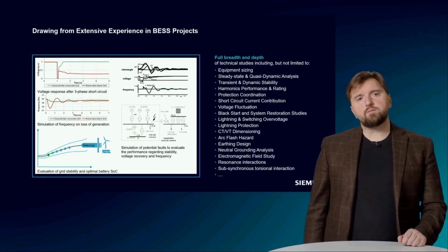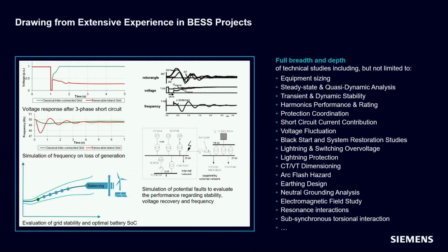When it comes to performing specific technical studies, Siemens PTI does more than just run standard tests. Through our studies, we cover a wide range of aspects. More importantly, we provide tailored advice to our clients regarding the necessary studies for their project. So depending on the circumstances and specifics of the project, we may recommend different approaches and types of studies. A lot of it will depend on the stage a project is in, but it may also depend on technical grid parameters around the project. For instance, if weak grid conditions are identified at the interconnection point, we may advise performing additional EMT analysis alongside RMS for dynamic and transient studies.